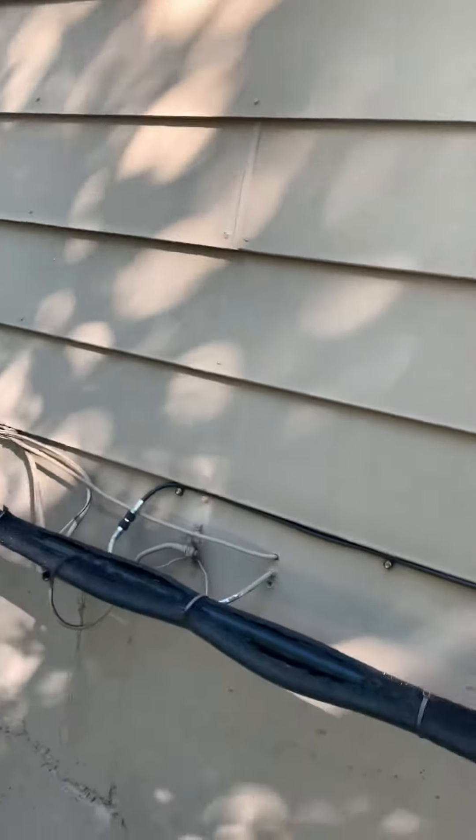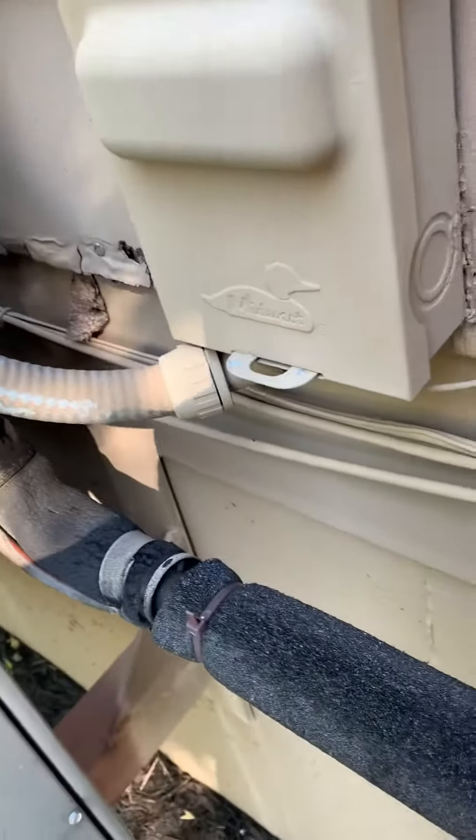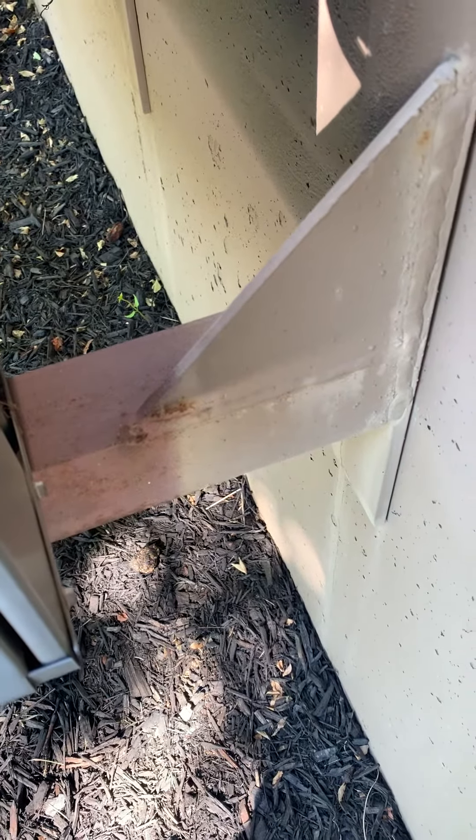We don't know the history of any of this. If I get that refrigerant out, put ours in, and then just put new insulation all the way across — this is inch and an eighth. New disconnect, new electrical whip. You can see the bracket there, so we'll do what we need to do and make the proper modifications.